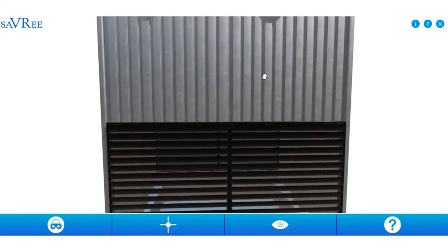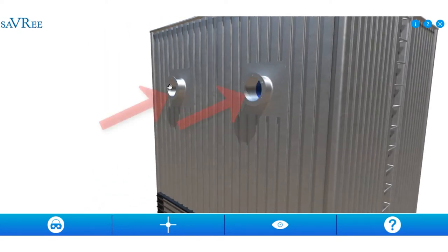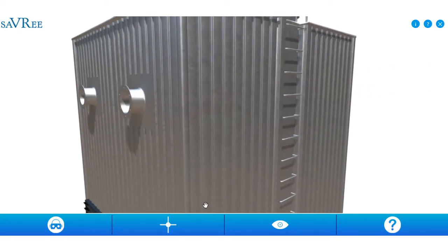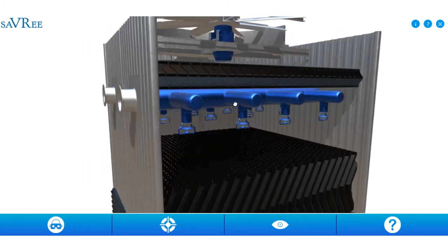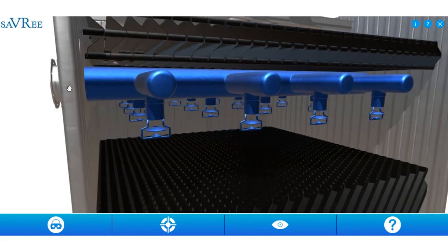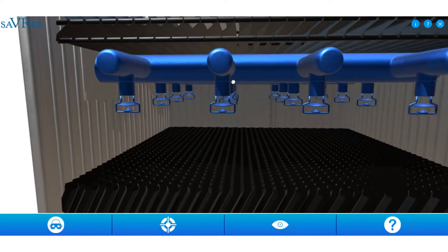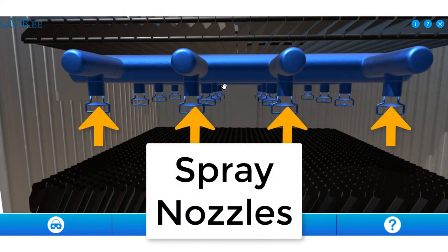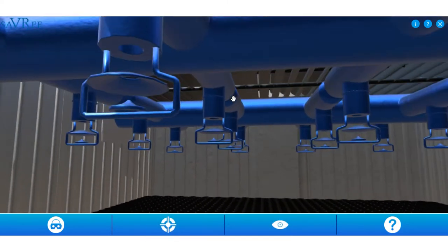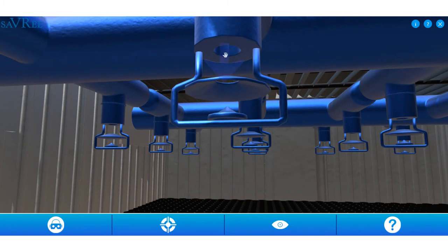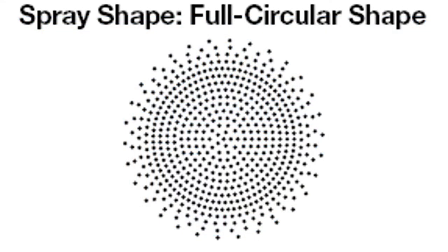Let's follow that through. We're going to be getting warmer water into these two pipes here. Taking a cross section, the warmer water comes in through the pipe and it's going to be distributed through these blue items, which we call spray nozzles. The water is going to shoot out the hole, impact onto this disc here, and spread out into a round circular pattern, creating a lot of raindrops — a raining type of effect.